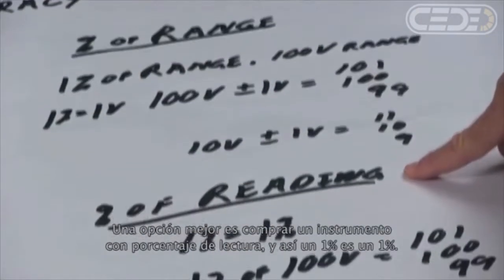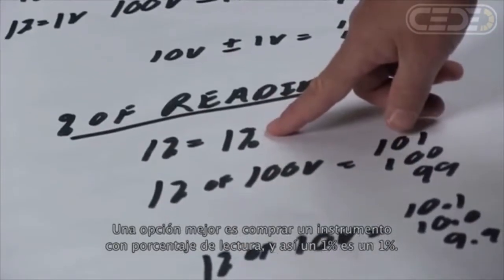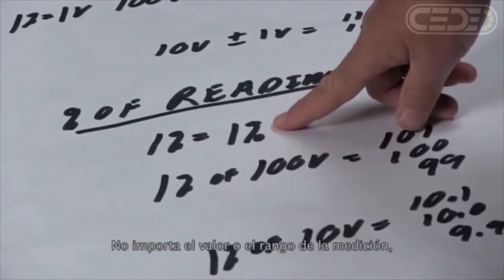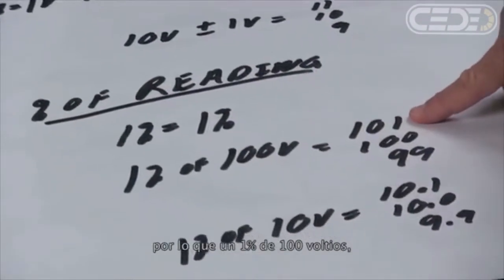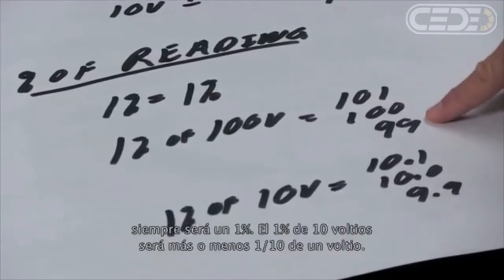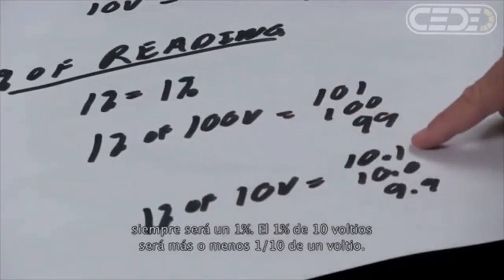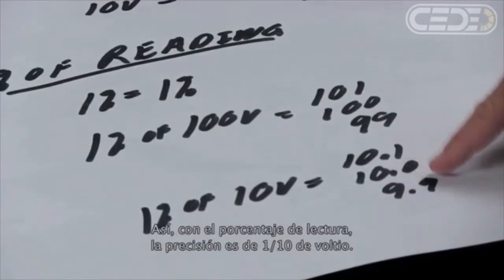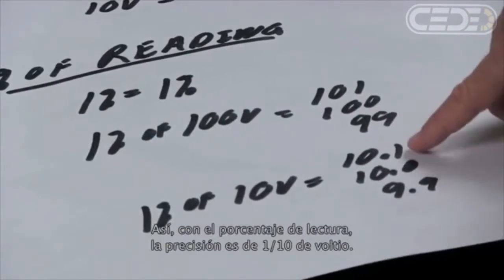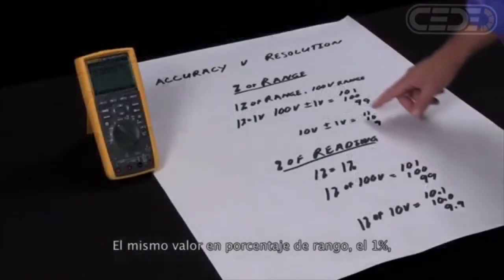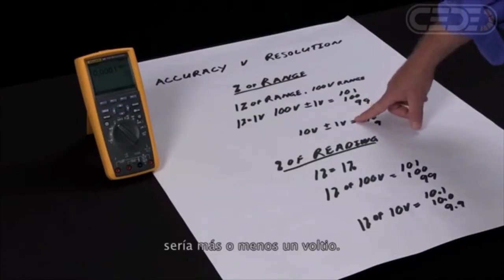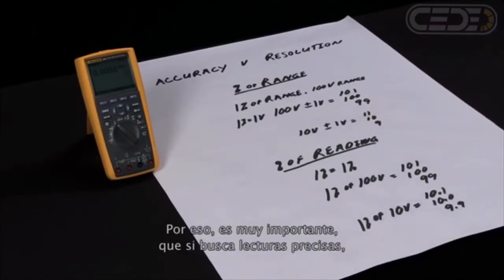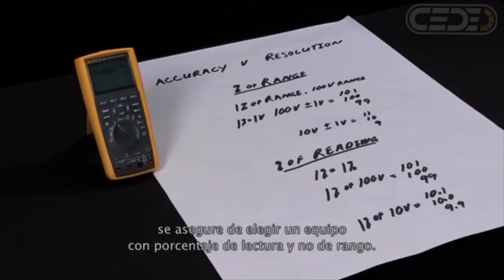A better way is to buy an instrument that has percent of reading — then one percent is one percent, it doesn't matter what value or what range you're on. One percent of a hundred volts is plus or minus one volt. One percent of ten volts is plus or minus a tenth of a volt. So it's very important if you're looking for accurate readings to make sure you select a device with percent of reading versus percent of range.